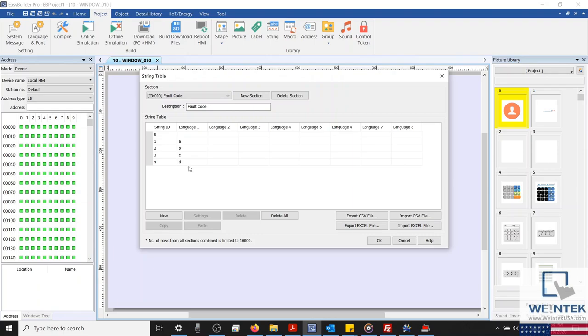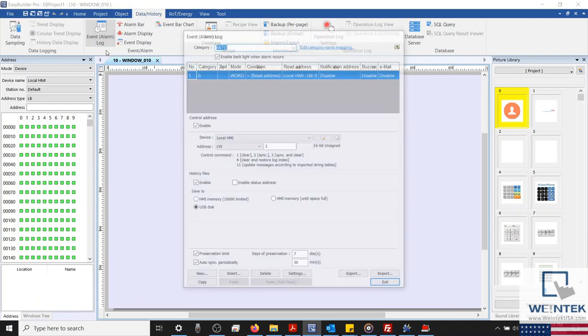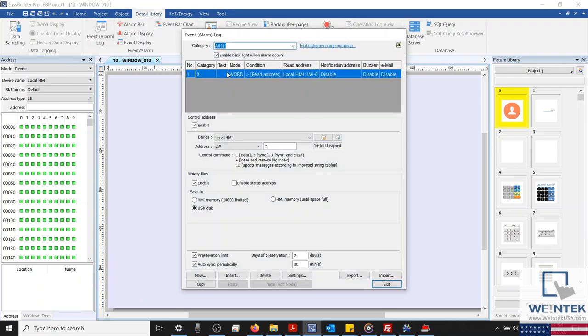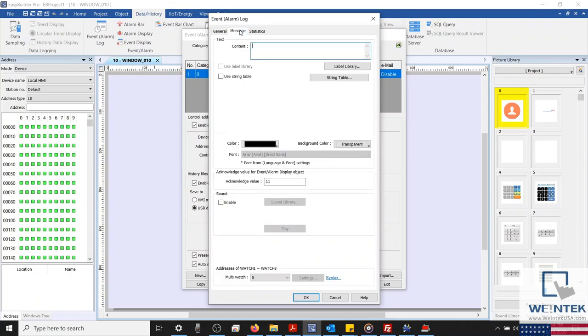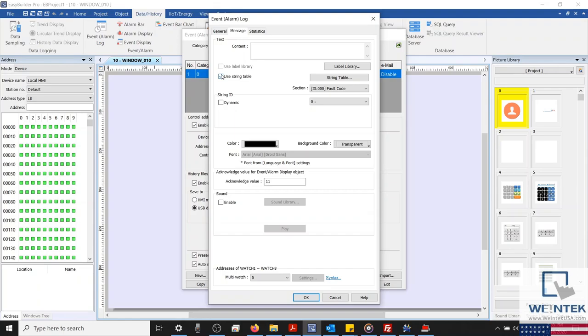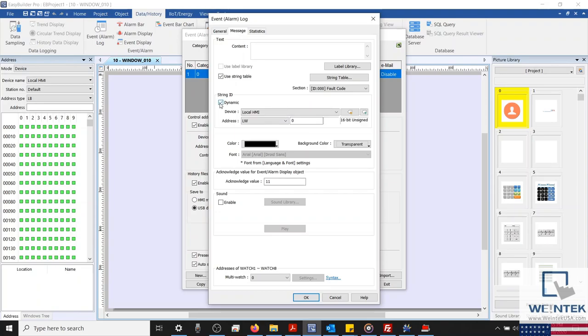With our string library complete, let's exit our library and open our alarm. Now, in our message tab, you'll see that our string library section is no longer grayed out. And so we'll enable this. And now within our string ID section, I can select a specific string from within my created section or define a dynamic string entry. I'm going to enable dynamic for this example and configure our dynamic address so that it targets our alarm's read address.